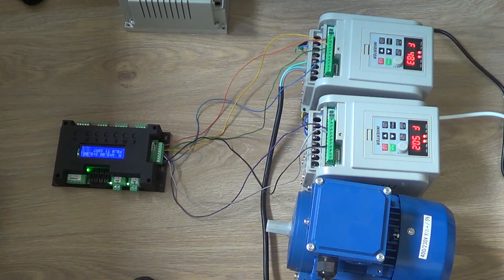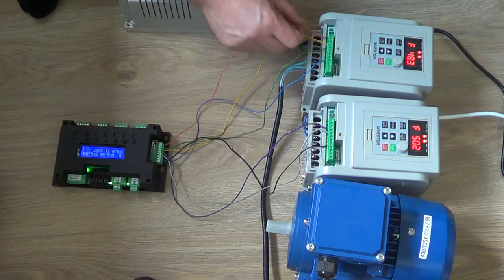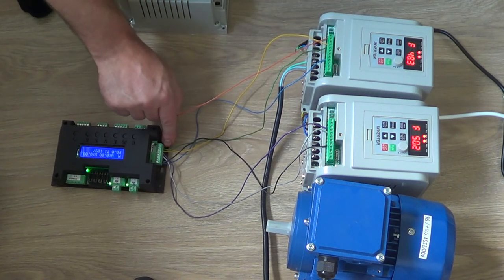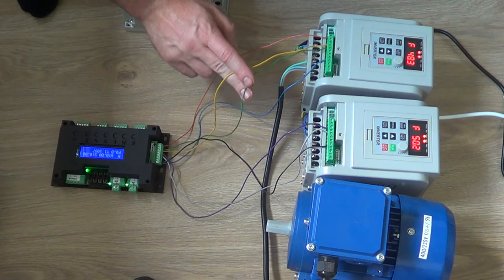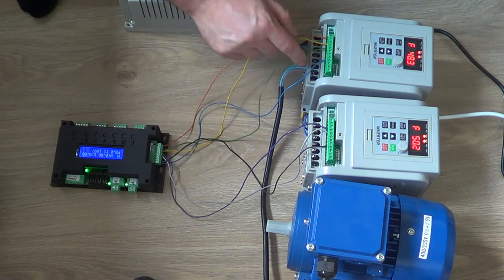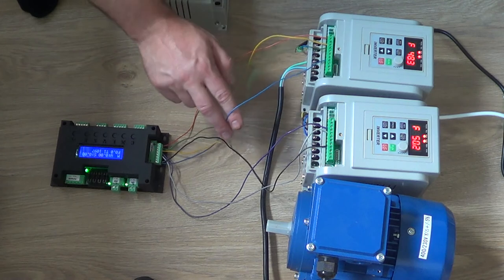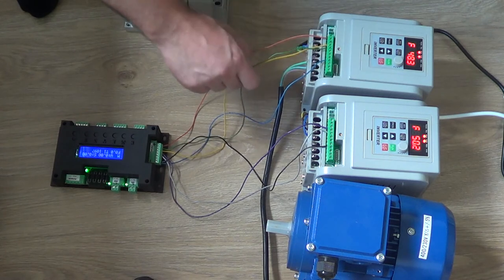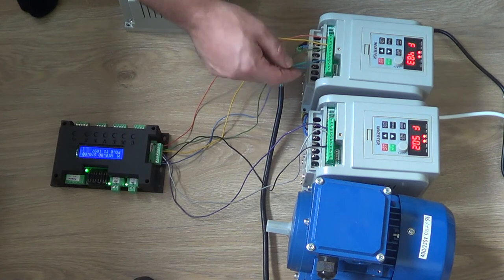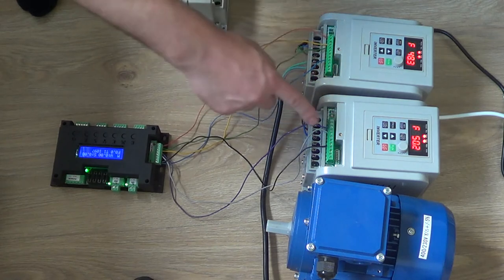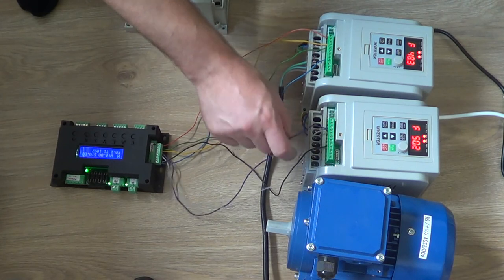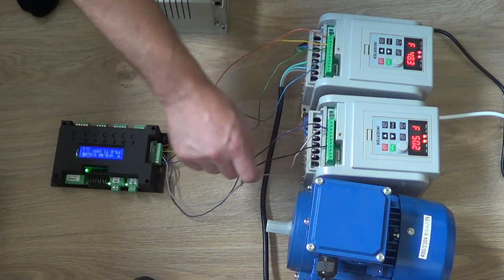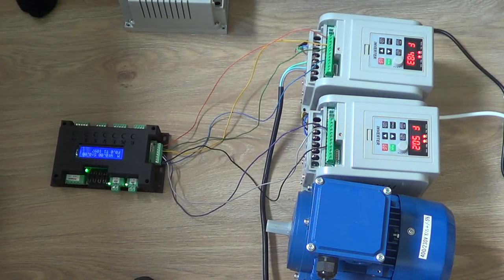About the cabling. Of course one of the inverters I will use as a power supply. That's why I have connected this wire to this first slot as a plus. And then I have two wires to control directions. So you have the east-west, then one wire to COM port which is just a ground to make sure that you have the ability to control the signals right. So those two signals will not work without this wire. Of course in such case this wire is for the power supply because it's just a minus and that's just a plus. In that case you don't have a plus, you have a minus and you have two direction wires, just north-south. And this wire is just the ground to make sure that the signal will go through those cables right.